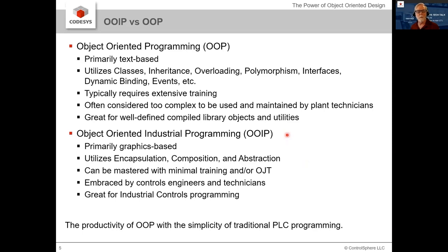Object-oriented industrial programming, on the other hand, is primarily graphics-based. Engineers tend to be more graphically oriented, so graphics-based languages like CFC and sequential function chart are more popular. OOIP only uses a subset of object-oriented programming — encapsulation, composition, and abstraction. Because we only use this simple subset, it's very easy to master and easy to understand, and can just be learned with on-the-job training. Everyone that's tried it embraces it and loves it. It gives you the productivity of object-oriented programming without all the complexity.